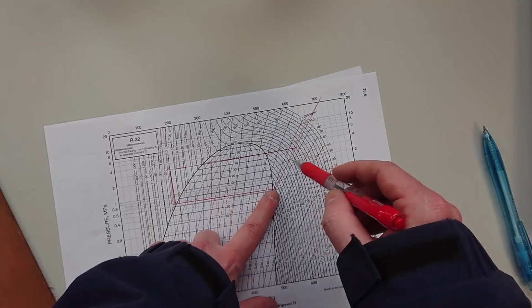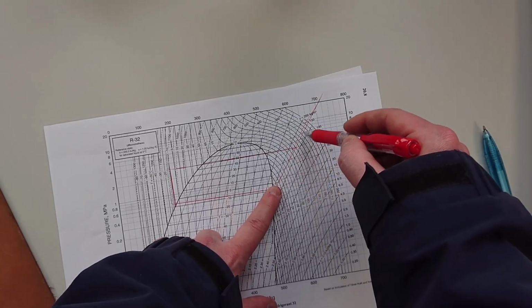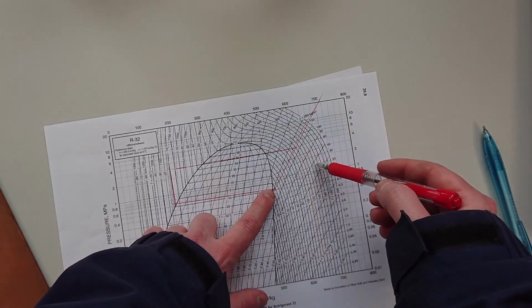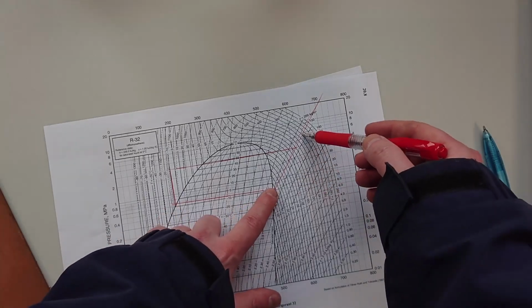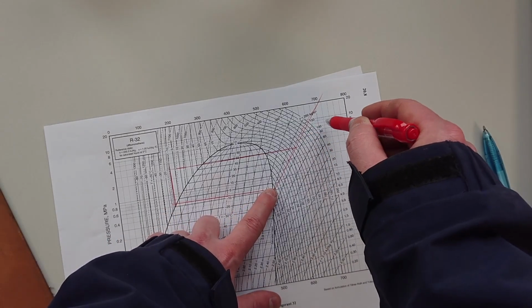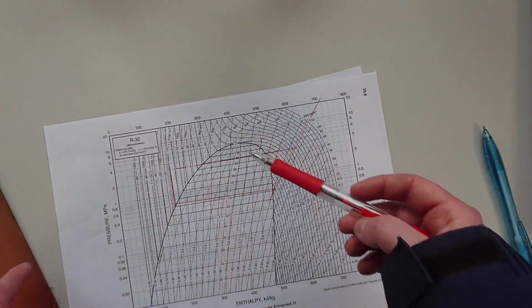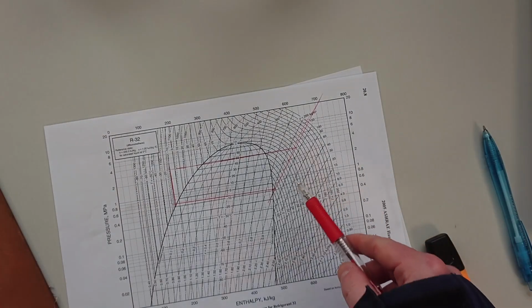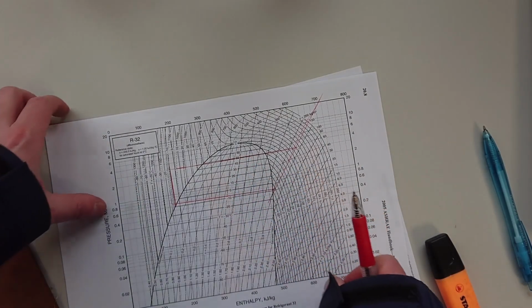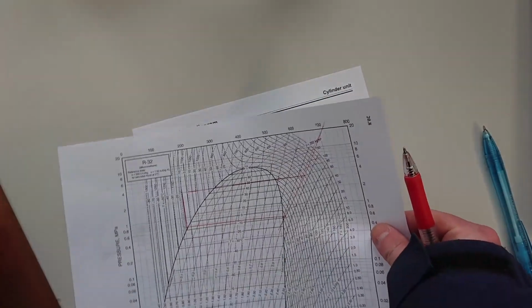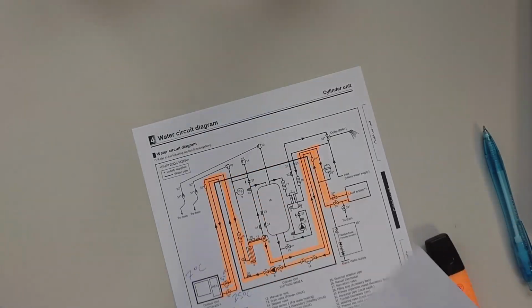So we can't raise this pressure any higher to be able to compress the same amount and come up with a higher pressure. So as we do this, the system gets more and more inefficient, and it takes you more and more energy to compress it to the higher amount as you come over here further, which means that your COP actually drops. So there is some point when it becomes most efficient for your compressor to run, and that's the bit that makes you buy the system. So that's what the manufacturers aim for.